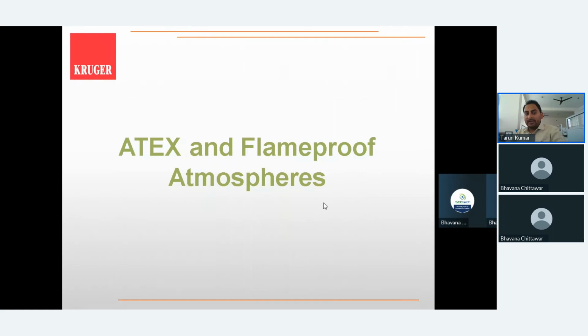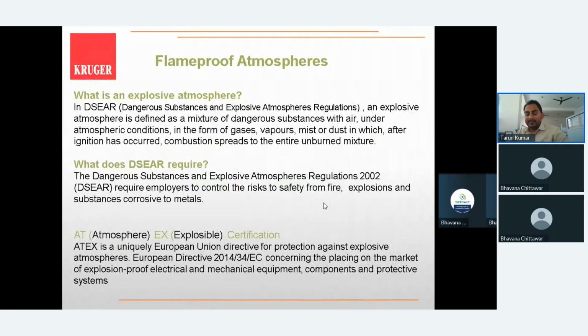Further to that, ventilation for flame proof atmospheres. There are multiple guidelines for explosive environments, with classifications from different bodies. They ask that the fan be ATEX certified. ATEX is the body which certifies that a fan is completely flame proof or spark resistant type.